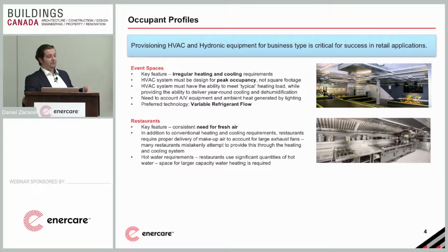They think, oh, I've got a rooftop unit that's providing me with my heating and my cooling, but that's circulating the air throughout your property. You supply heating and cooling, it comes back through the return. A little bit of outdoor air is brought in at the same time, but it does not make up for your exhausted air. The exhausted air is sized for specific reasons, and then your makeup air will be sized based off of the exhausted air that comes out of your property. So without having a unit like this, it creates discomfort for the tenants and the clients and people you have in your properties, as well as for the equipment that you have in your property.